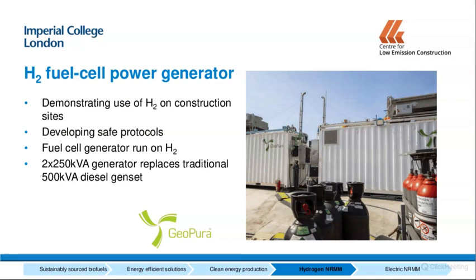Sticking with hydrogen NRMM, but moving on to the power generation. This project, the hydrogen fuel cell power generator, demonstrated the use of a hydrogen fuel cell generator on an active construction site. The GeoPura power unit is a 250 kVA generator, which replaced a traditional 500 kVA diesel generator. This unit was run for roughly 6 to 7 months on an active construction site in London, and it demonstrated the use of hydrogen in construction and helped develop protocols for the safe use of hydrogen on site. Since there are no tailpipe emissions from a hydrogen fuel cell, the emission benefits were quantified from coupling measured emission factors of the replaced diesel generator with the site activity profile for the duration of the project.